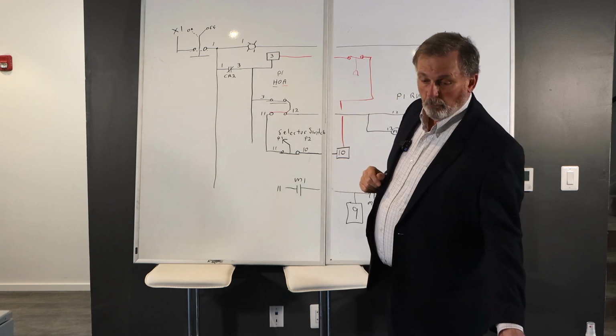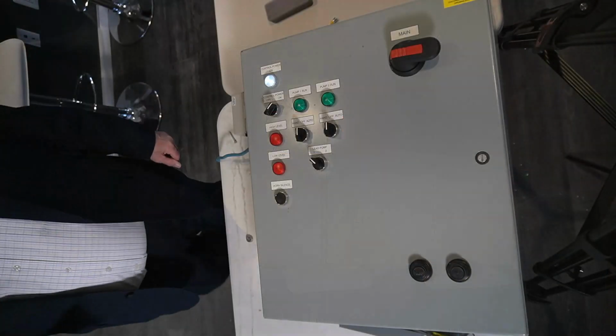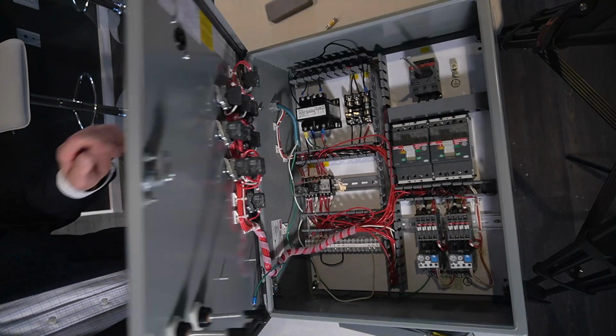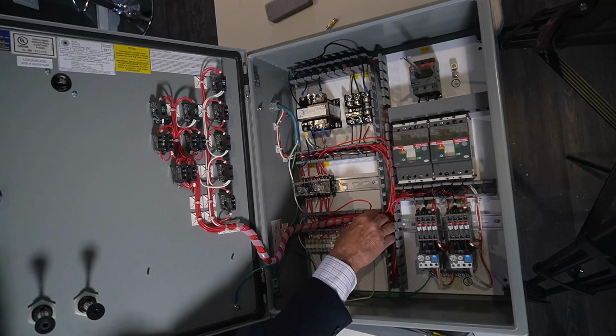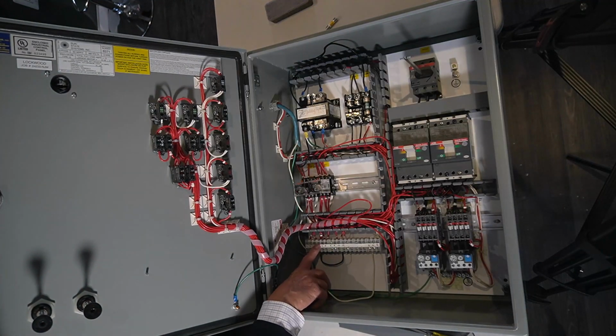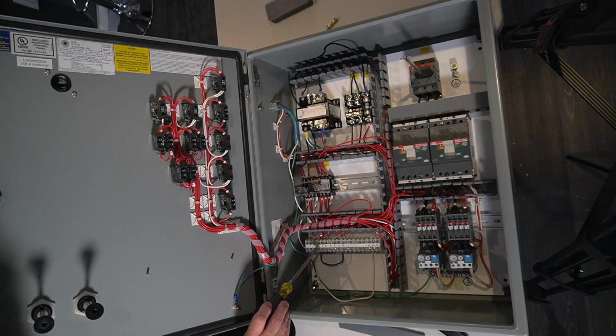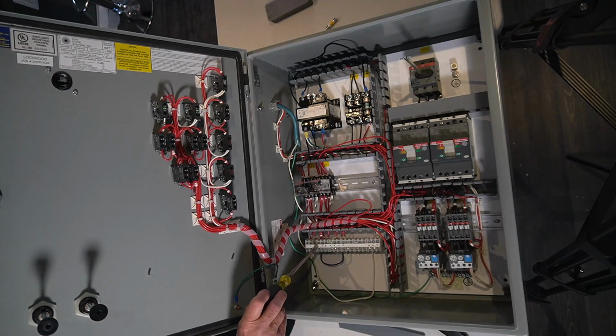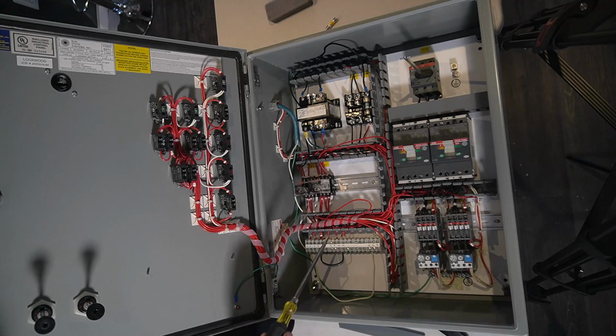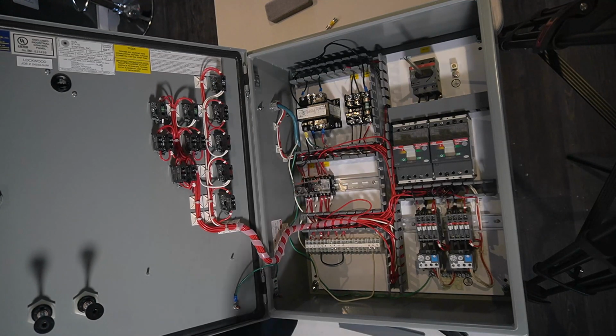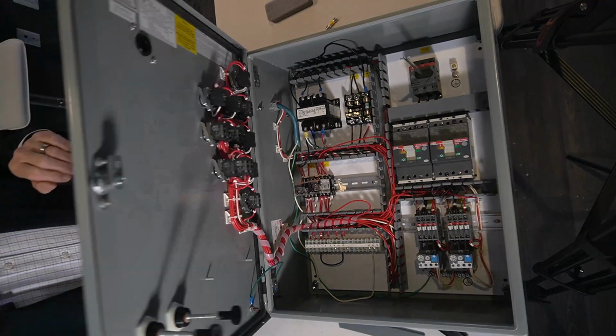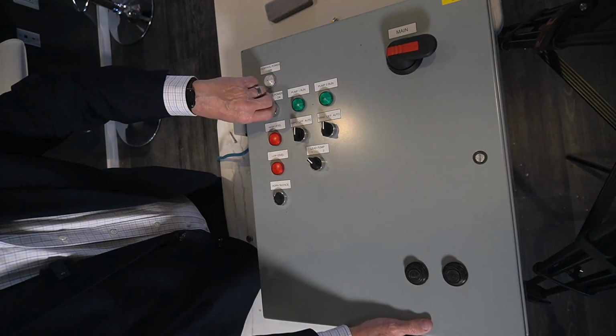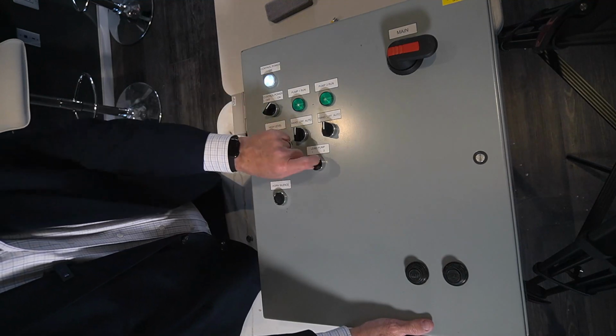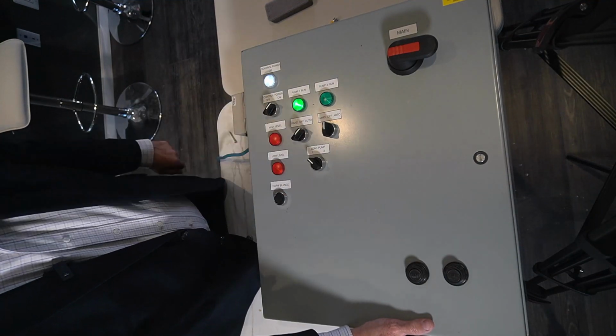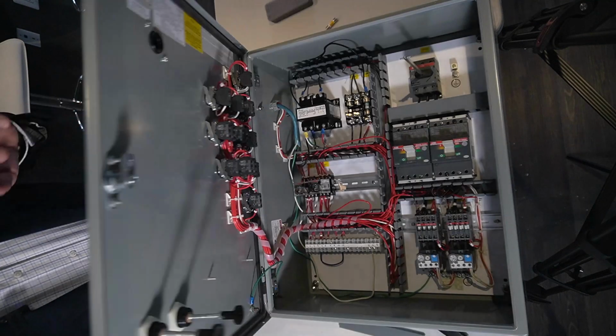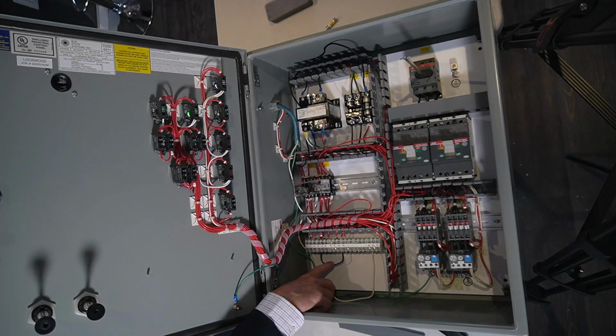So what I've done to make this work is I put a jumper inside the control panel from wire number 3 to wire number 10. That's wire 3 and wire 10. 3 is a hot off of the relay, and 10 is the input for the automatic operation of the pump off of the level switch. So, control power on. I'm going to select lead pump 1. I'm going to go to auto, and it's going to energize. Okay? That's because the jumper is simulating that switch.